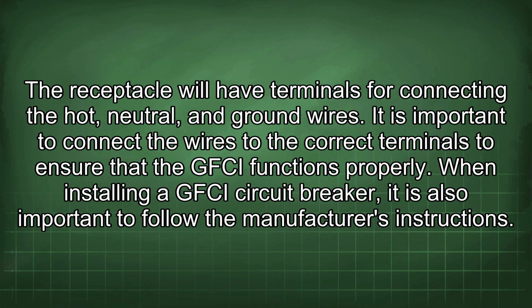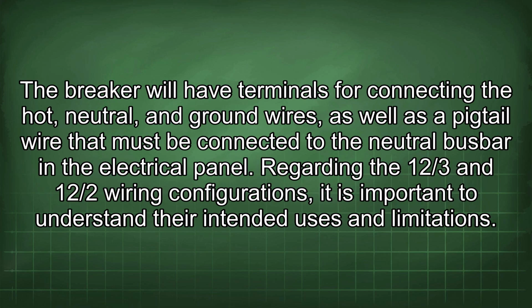When installing a GFCI circuit breaker, it is also important to follow the manufacturer's instructions. The breaker will have terminals for connecting the hot, neutral, and ground wires, as well as a pigtail wire that must be connected to the neutral busbar in the electrical panel.